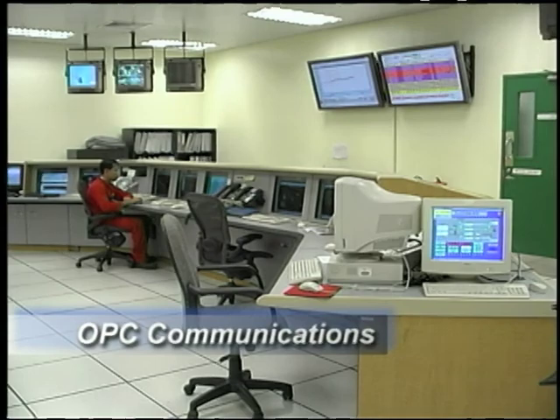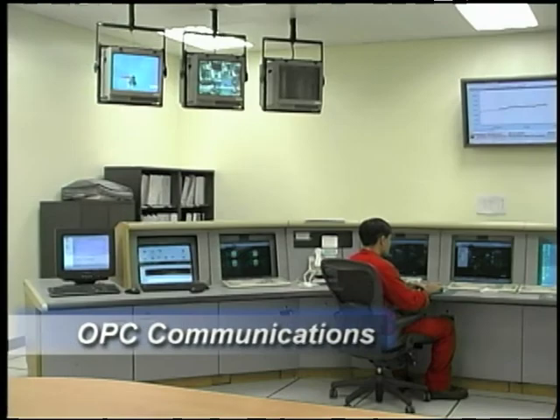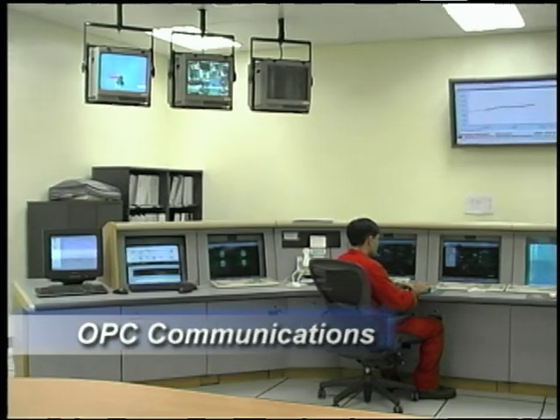The digital system's use of the OPC communications protocol lets Shell seamlessly integrate disparate systems and equipment. By using OPC, we had a common form of communication between the Delta V platform and the third-party equipment, but it also made all the information from the third-party equipment available to everybody. So at the moment, if the vendor of a compressor wants some information on his own package, needs to know some process information, some safeguarding information, all that is available to him via OPC.